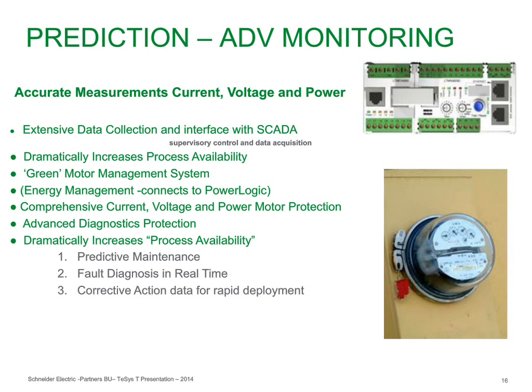And if you look to the bottom there, there are really three big benefits in this process: availability or uptime, predictive maintenance, which is knowing when equipment is operating outside of its norm, and being able to have fault diagnostics as to what is the fault. Is it an overcurrent? Is it an undercurrent? Over voltage, under voltage? It could be a power factor problem. You can get all that data out of this particular unit to have real-time diagnostics of the faults or the alarms, and then you can do a corrective action, knowing what you need to fix and where you need to fix it, oftentimes before the device will actually fail.